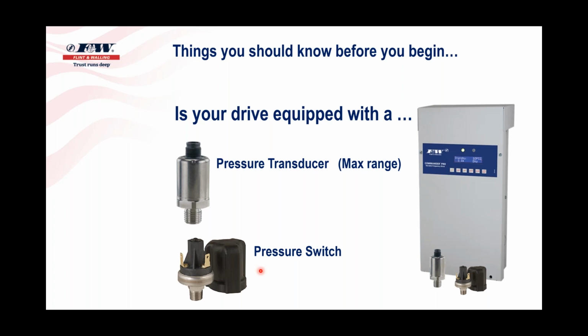And I know that one particular contractor looked at me and said, now, what type of transducer are you using? And I looked at him and I said, well, we're not using a transducer. We're using a pressure switch. I don't like those. And I mean, I really don't like those. So tell you what, son, if you can ever make that drive operate on a pressure transducer, come on back, talk to me. We may have something to talk about. He didn't like the switch. So we ship them both ways.